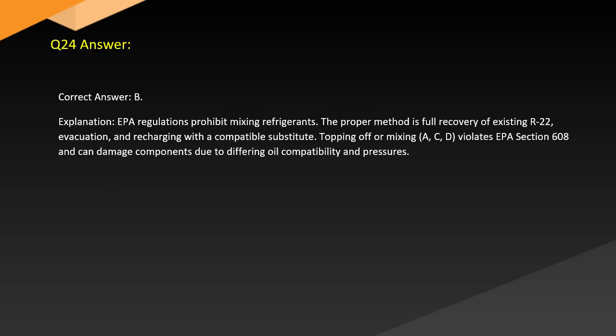Answer. Correct answer: B. Explanation. EPA regulations prohibit mixing refrigerants. The proper method is full recovery of the existing R22, evacuation, and recharging with a compatible substitute. Topping off or mixing (A, C, D) violates EPA Section 608 and can damage components due to differing oil compatibility and pressures.